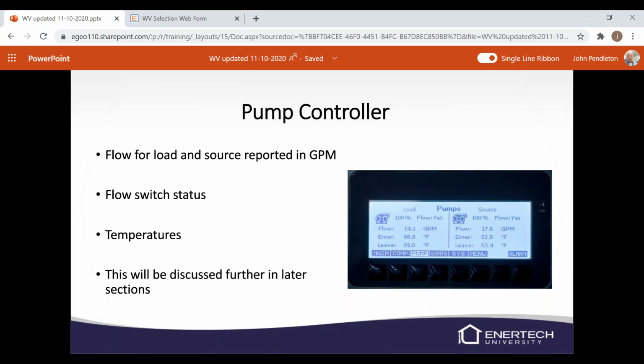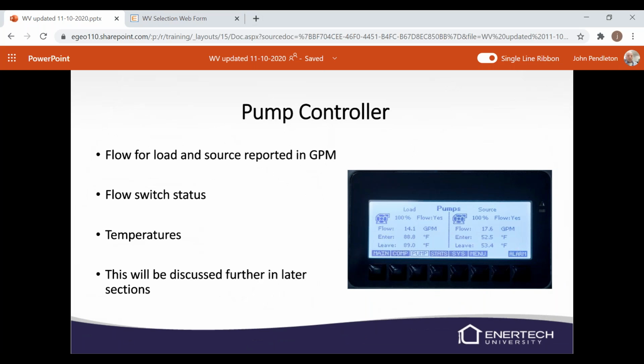This is the pump controller. You can actually go, when you get to the HMI, the human machine interface, it's kind of hard to see in this picture here, but if you'll see on the bottom it has those dark colored boxes, it says main, comp, pump. But you can see the pump, it's kind of whited out there. There's actually a button below that. So if you were to press main, it'll go to your main screen. If you press compressor, it'll go to your compressor screen. If you press the pump button, which is right underneath where it says pump, it'll take you to your pump screen. Now, you'll see like a little volute there. It'll have these little black boxes, and they'll be spinning if the pump is moving.